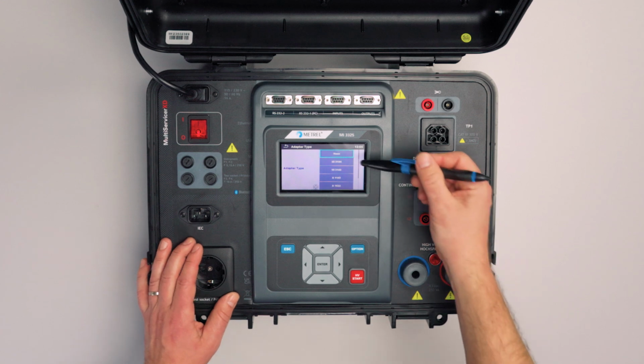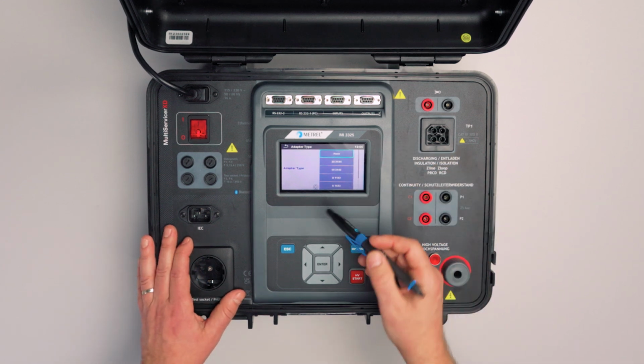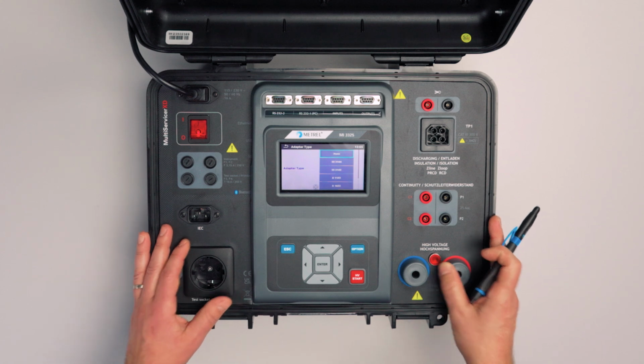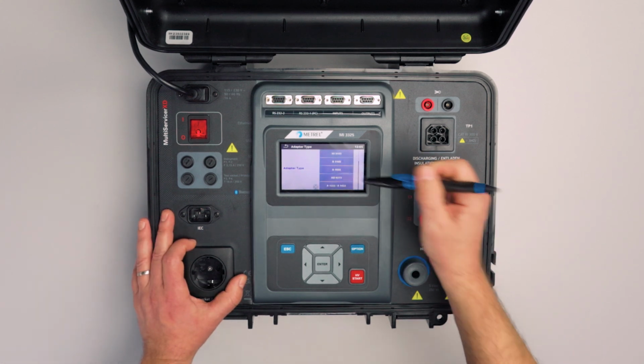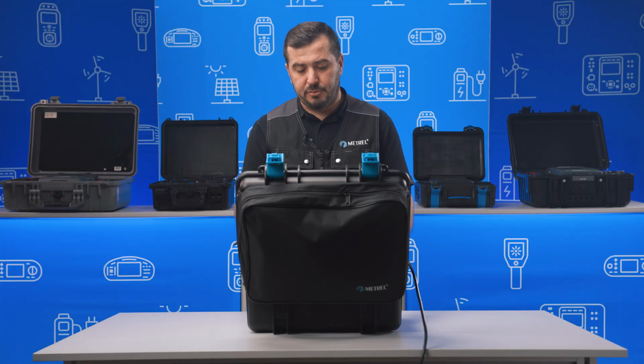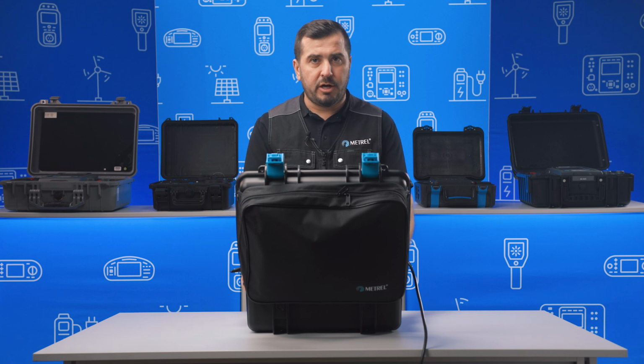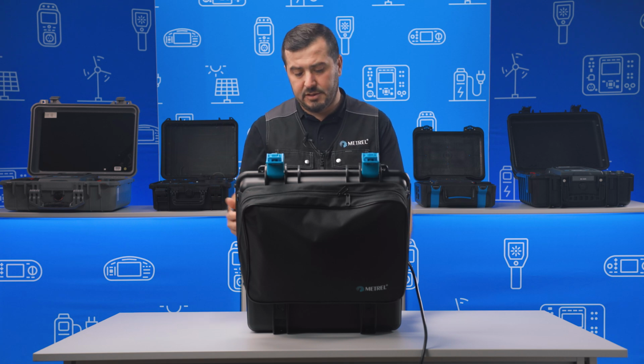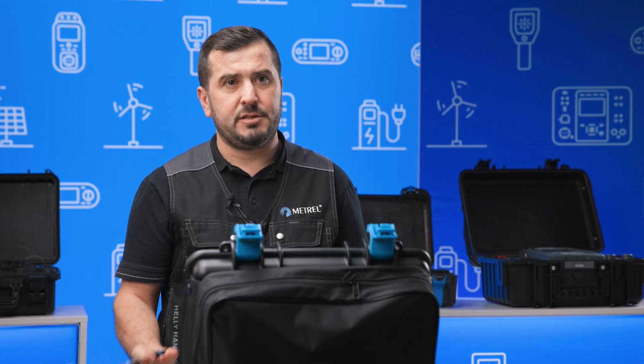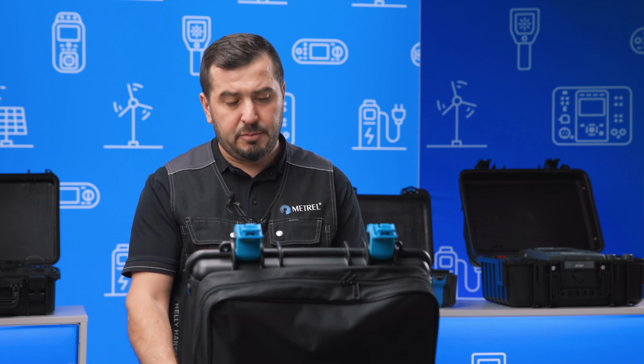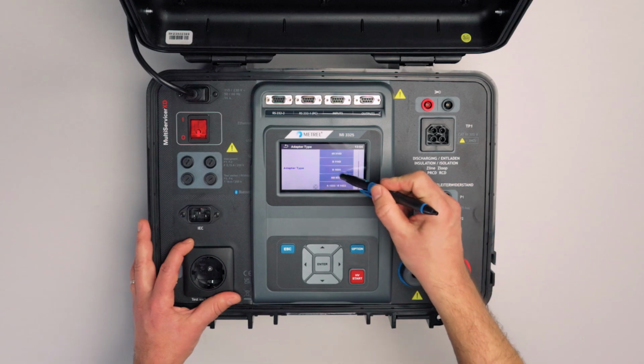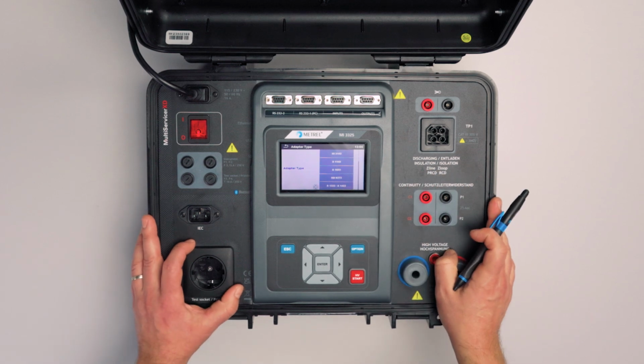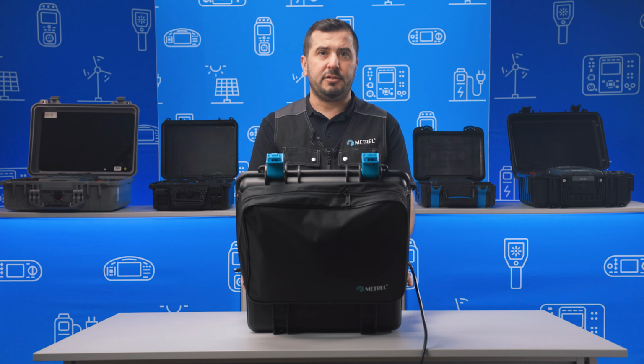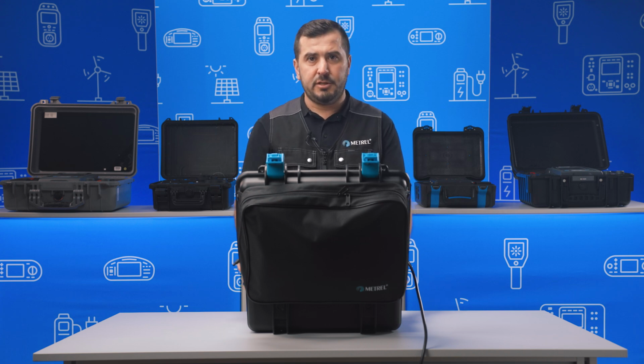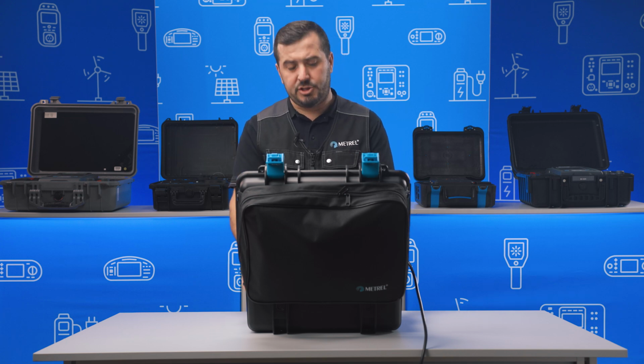What are the options? The first two options, the MI3144 and the MI3143, are for the impedance adapters. So in case that we are performing measurements in switchboard environments where we need higher currents for performance of line loop impedances, we always recommend to use these external impedance adapters for more accurate measurements. Then the instrument also supports the A1632 adapter. This one is specially dedicated for testing electrical vehicle safety equipment, in particular charging stations.